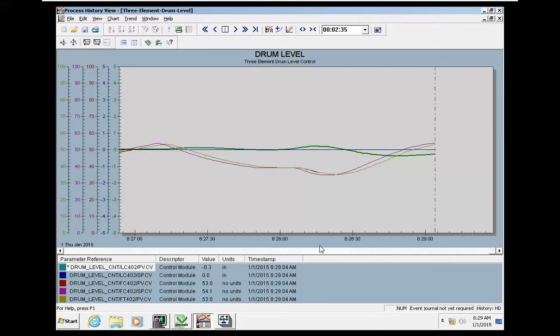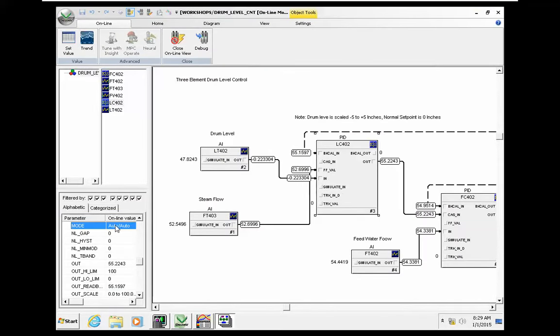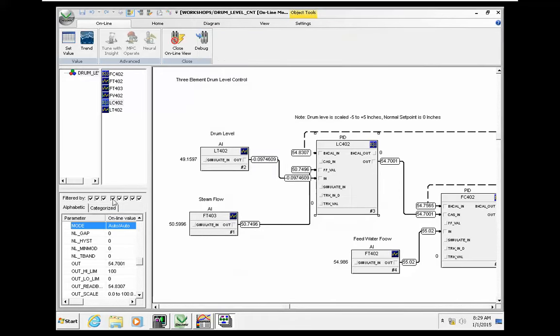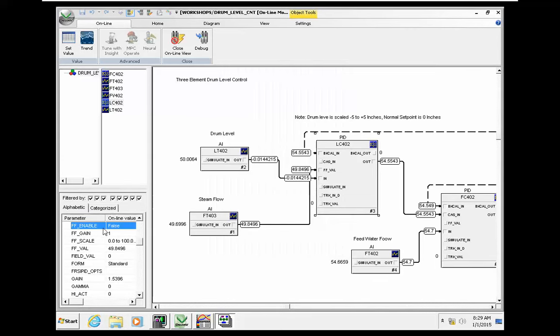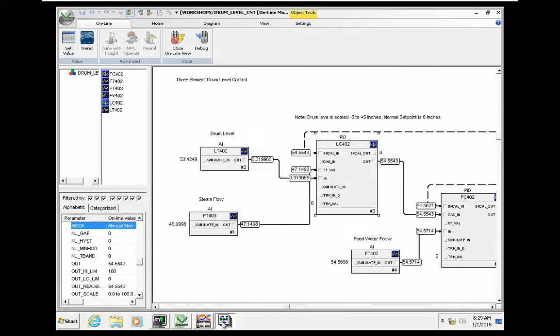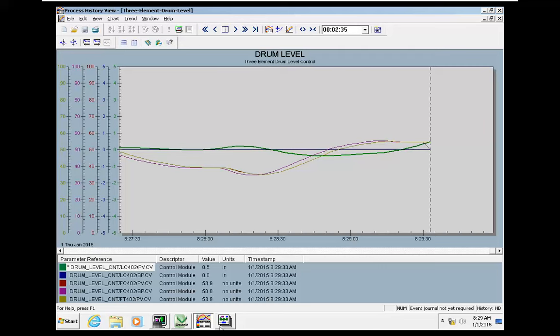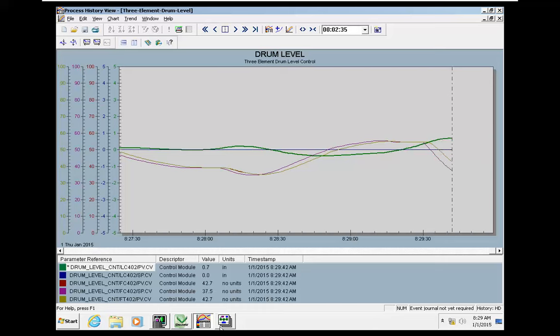Let me enable the feedforward. I need to put the PID in manual, FF enable, enable the feedforward true, and change the mode to automatic. Wait for a while to reach the steady state because we were in manual and now we are going to automatic mode.